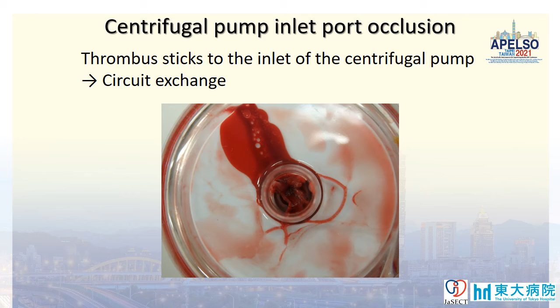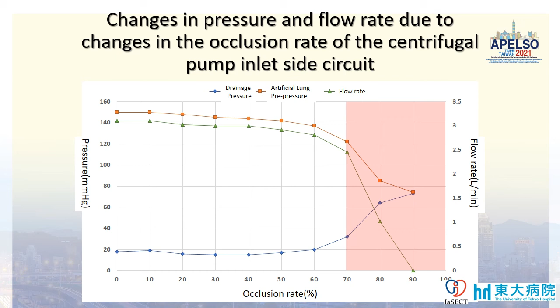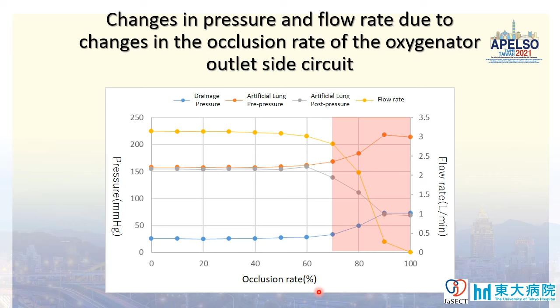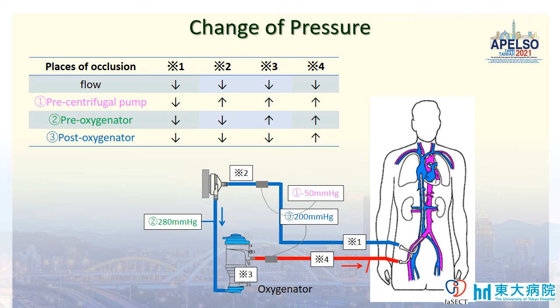This slide shows the changes in pressure and flow rate due to changes in the occlusion rate of the centrifugal pump inlet side circuit. This graph shows that significant changes in flow rate and centrifugal pump pressure occur when the occlusion rate exceeds 70%. That's why we must prepare for circuit exchange quickly if we detect these changes. This graph shows that the same can be said when the transmembrane pressure gradient rises. This table is a common one, but we should recognize that more than 70% of the circuit is occluded when the changes in pressure or flow rate appear.